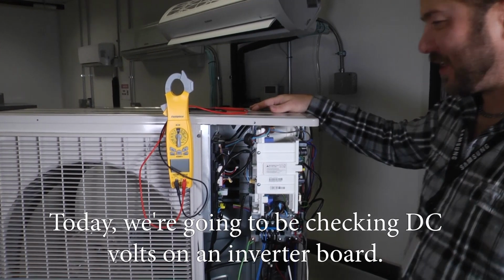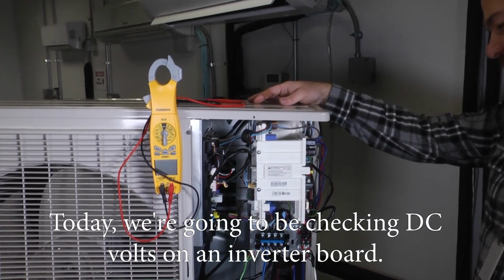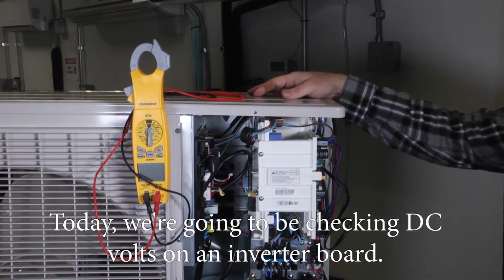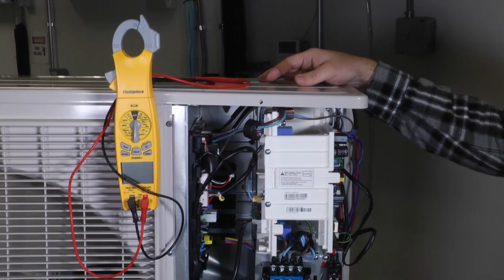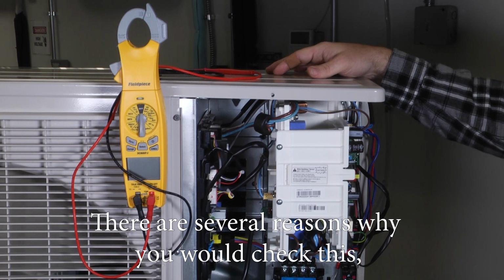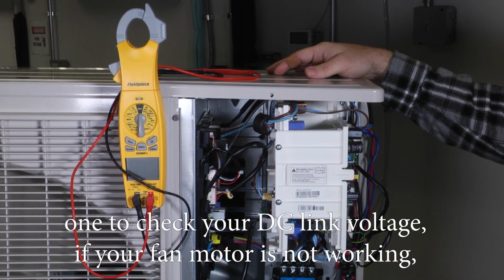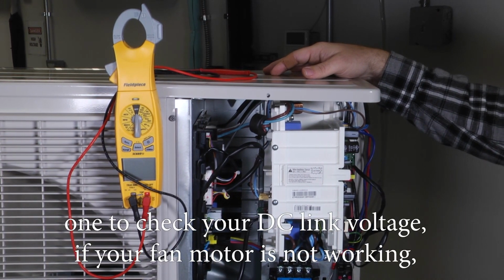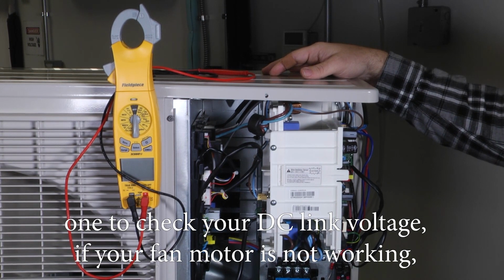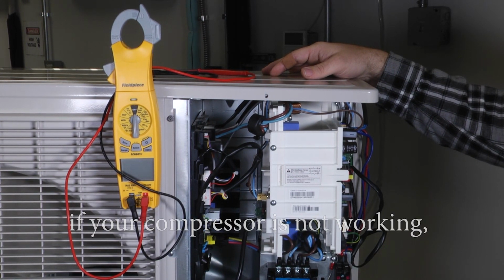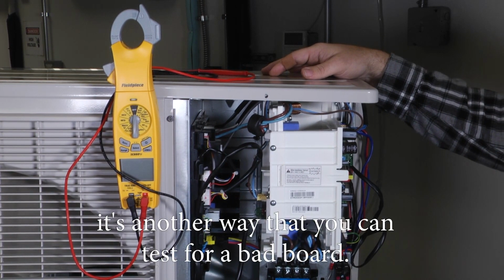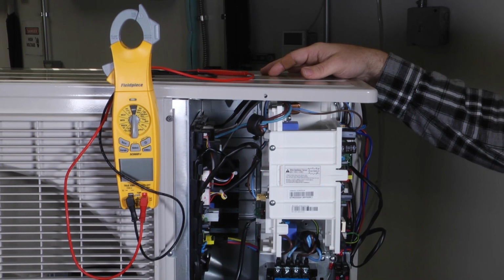Today we're going to be checking DC volts on an inverter board. There's several reasons why you would check this. One, to check your DC link voltage. If your fan motor's not working, if your compressor's not working, it's another way that you can test for a bad board.